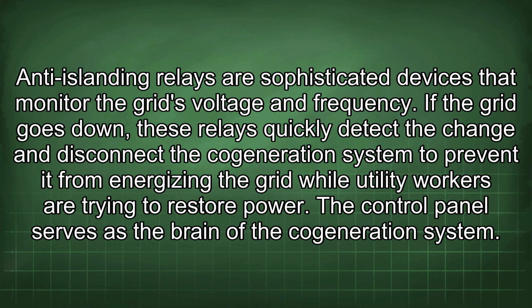Anti-islanding relays are sophisticated devices that monitor the grid's voltage and frequency. If the grid goes down, these relays quickly detect the change and disconnect the cogeneration system to prevent it from energizing the grid while utility workers are trying to restore power.